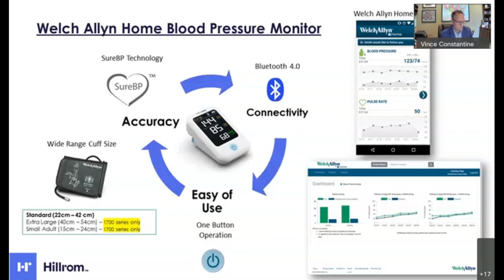This talks a little bit about the Welch Allyn Home app. This is a very simple one-time setup. You download the app from the App Store or the Google Play Store, and this is where the readings reside once they're taken from the device. The device has memory for 99 readings, but once it connects with the app, all those readings download. So if a patient forgets to have their phone on or near them or near the device when they take the reading, and they take maybe 3 or 4 in that day, they're still stored on the device. Then once the device is in range, all those readings filter over to the app.